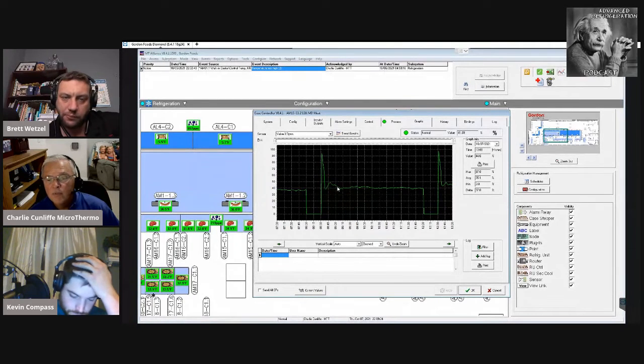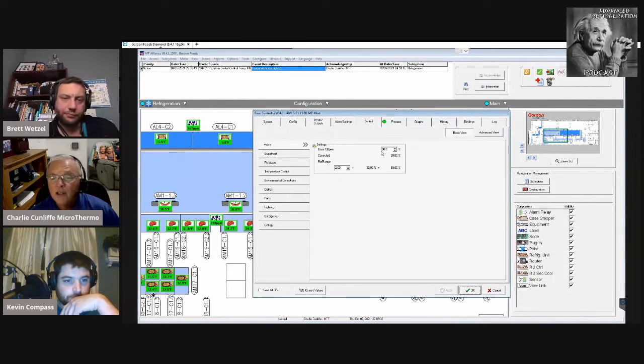So I close for defrost. I open wide right after defrost, and I drop like a rock as far as I can, and then I'm modulating right around 40%. So stay with me here. I'm going to go to control. And all right, he's got the base open of 30%. I might say it should be 40, but with those linear graphs, and the refrigeration range is 30 times 2, so the maximum this would ever go is 60.